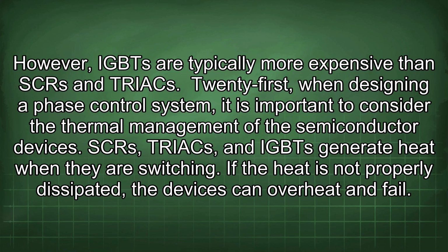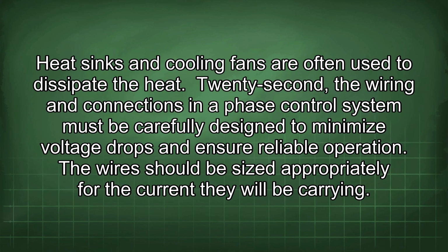21st, when designing a phase control system, it is important to consider the thermal management of the semiconductor devices. SCRs, TRIACs, and IGBTs generate heat when they are switching. If the heat is not properly dissipated, the devices can overheat and fail. Heat sinks and cooling fans are often used to dissipate the heat.